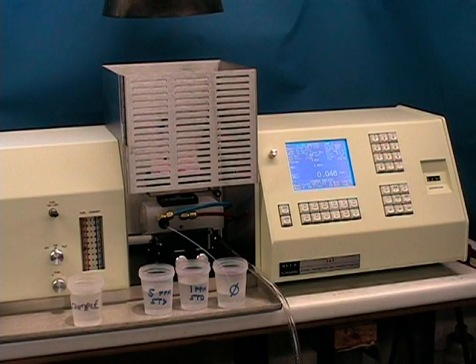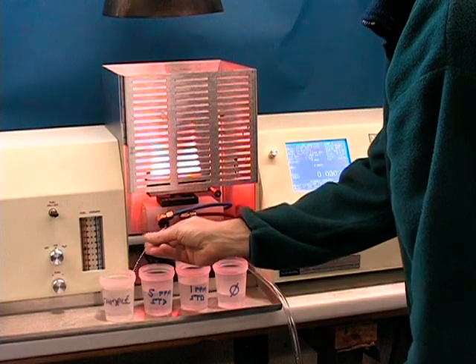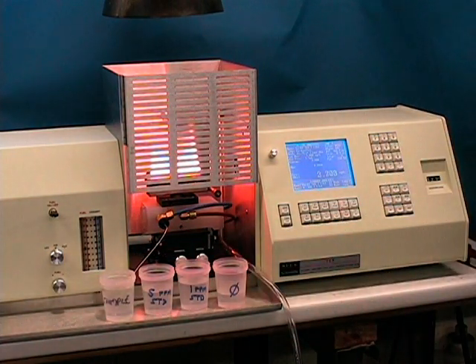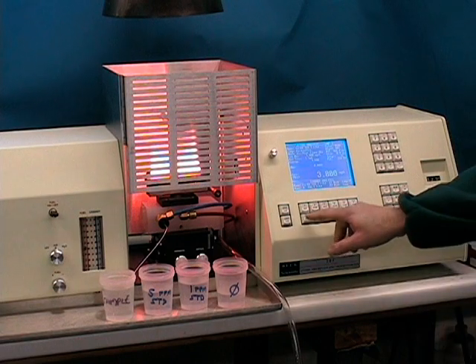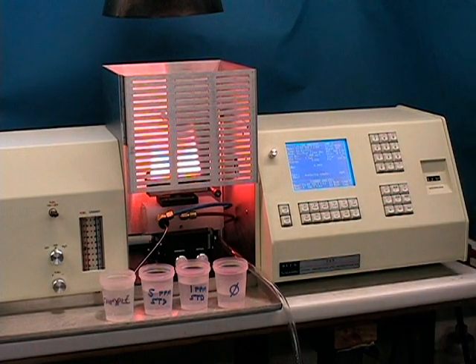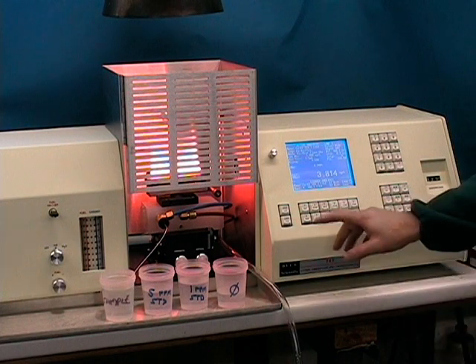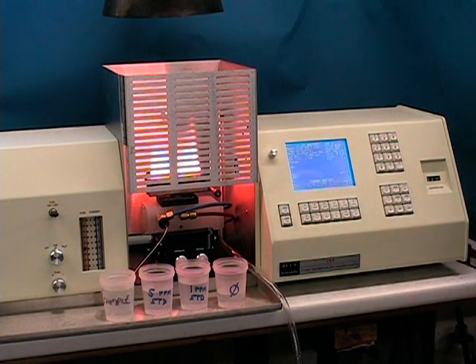Once you have verified that your blank and calibration standards are accurate, you may aspirate your sample, wait a few seconds for the reading, and in this case we can see the bright yellow flame is due to high levels of sodium. Press the read key to read your parts per million copper in that sample solution. Take several readings, and you will be able to average them out and generate some calculations for statistics for your sample.